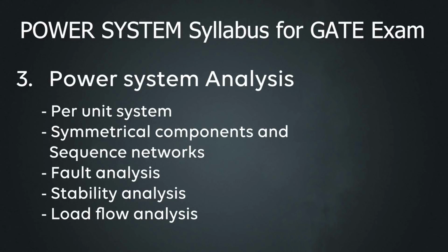And then fault analysis. Here we need to see fault current calculations for different types of faults, for example LG fault, LL fault, LLG fault, and three-phase faults. This fault current information is very important for designing the protection system - for calculating settings for protective relays and selection of circuit breakers. That is why we do fault analysis.